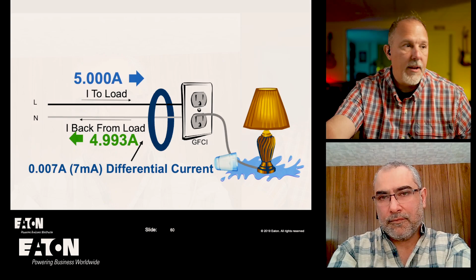Tom, this is the very reason GFCIs have been very successful, because as we've always said, it's a very unforgiving technology. If there's 6 milliamps, which is not a lot of current - just six-thousandths of an ampere - if it's missing somewhere, the GFCI doesn't care where it's going. It could be going through another circuit or something, but it doesn't matter, the GFCI would trip. This is the reason for the success of this technology.